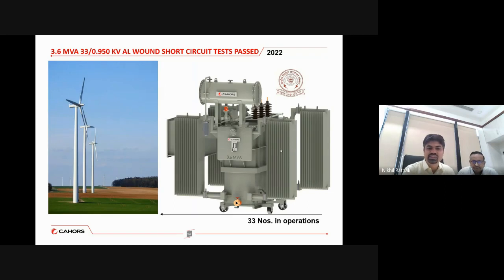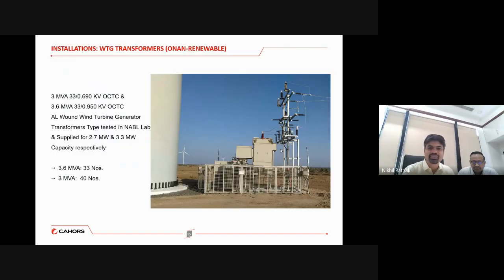Now, just to show you the product line, in our engagement in the renewable sector, we have done the type testing for 3.6 MVA specifically for the wind segment. And that is the reason we have supplied so far more than 33 transformers of 3.6 MVA and more than 40 transformers of 3 MVA, already installed in the renewable grid, which has contributed to a capacity of 300 megawatts. So this 3.6 MVA is mainly for a 3.3 megawatt wind turbine, and the 3 MVA transformer is mainly utilized for a 2.7 megawatt wind turbine. So this is the difference.